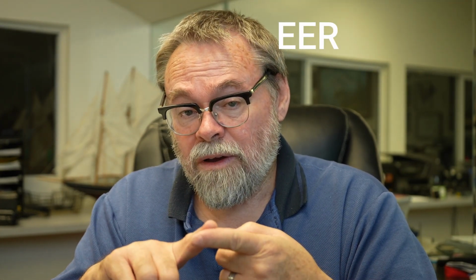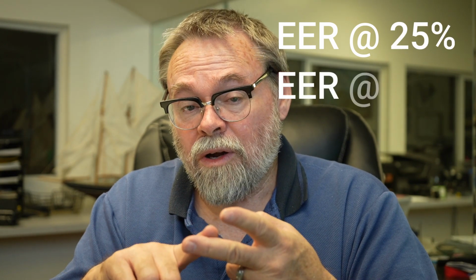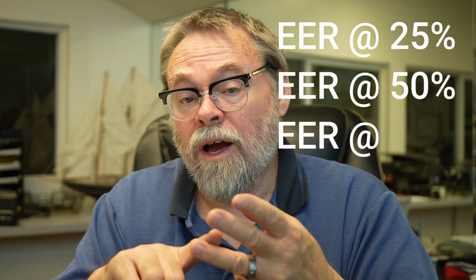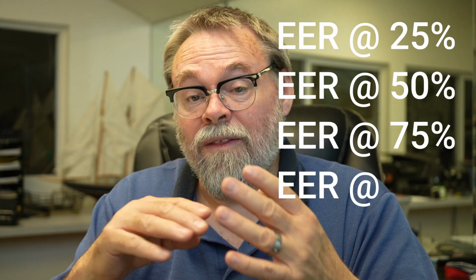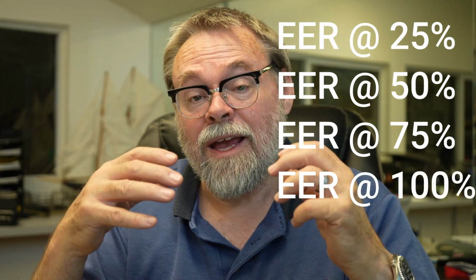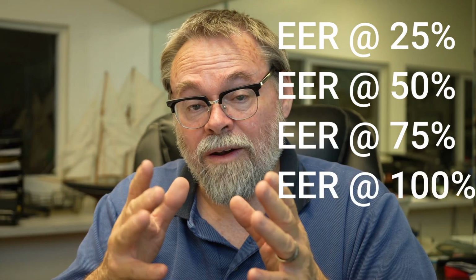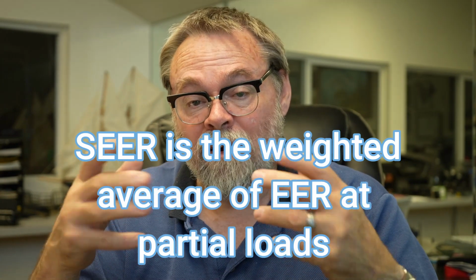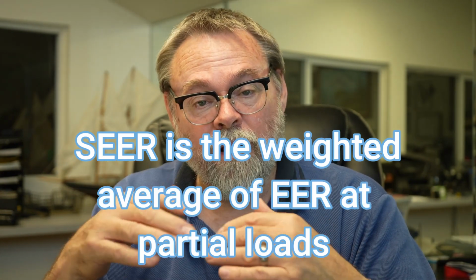That's considered the full load. Anything above that is above full load, anything below it is a partial load. To come up with SEER, they take the partial load EER at 25%, the partial load EER at 50%, the partial load EER at 75%, and then the full load at 100%. They can then average those out, and they come up with the SEER rating. In other words, that's an average of partial loads of the piece of equipment, and that gives them the SEER.